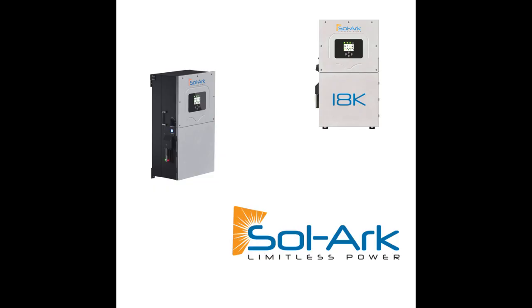Yeah, so this is just a really good example of what we're looking at, right? 600 amp service, 600 amp panel board, 3 inverters, 200 amps of pass through each, and you're good to go. System done, whole building backup. Yeah, you can keep going. So this is that photo that I was referring to earlier, where we're simply intercepting the essential backup portion of the panel that comes from the Sol-Ark, from the load output. Now we're providing millisecond backup for those buildings, and we are acting as the ATS, or the means of disconnecting from the utility.